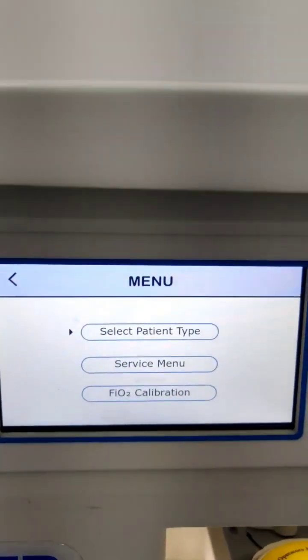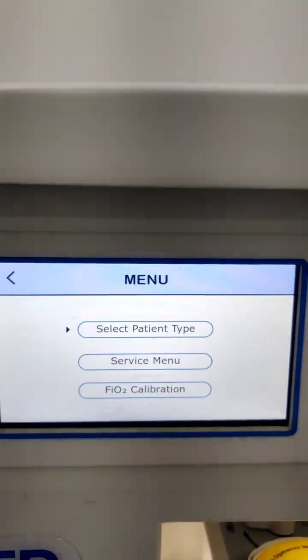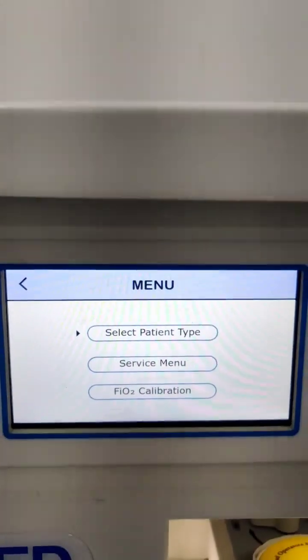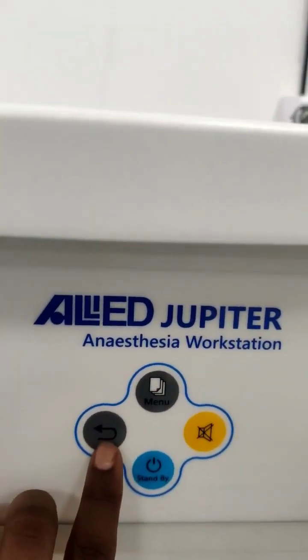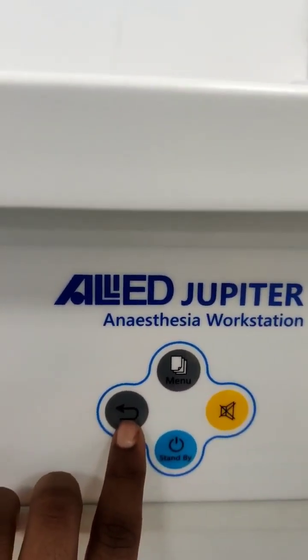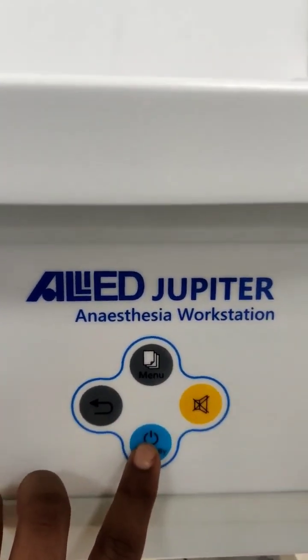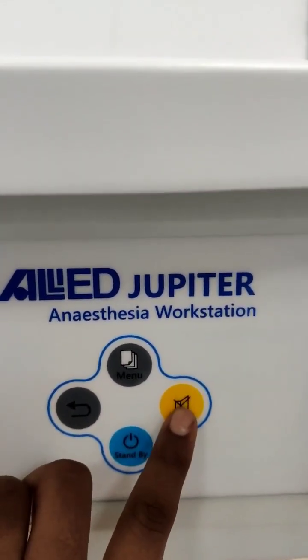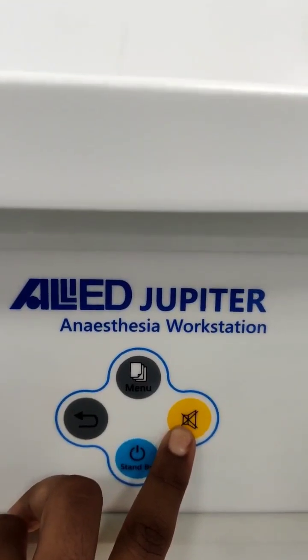As soon as I press the menu button, this window will come up. You can select the type of the patient, you can go into the service menu, and you can do the FiO2 calibrations. And this is the back button. For going back to the user interface screen, you can press this button. This is for the standby, and this is for silencing the alarms for 2 minutes, that is 120 seconds.